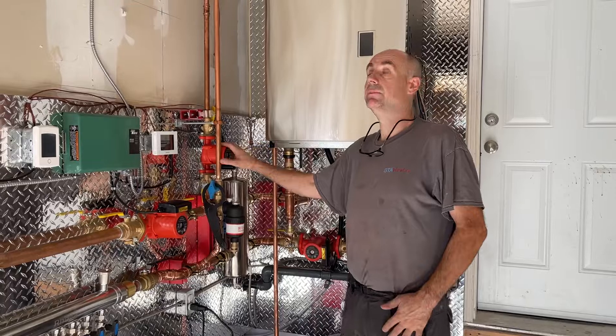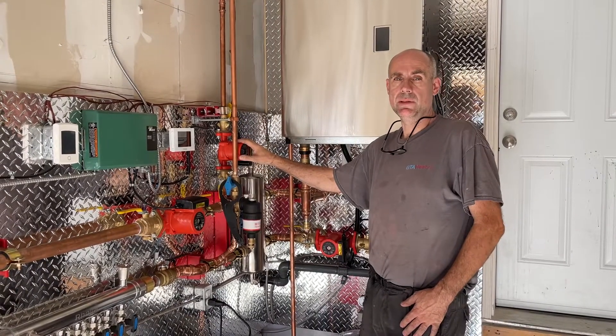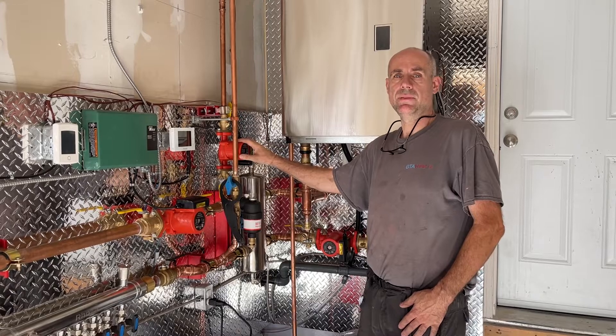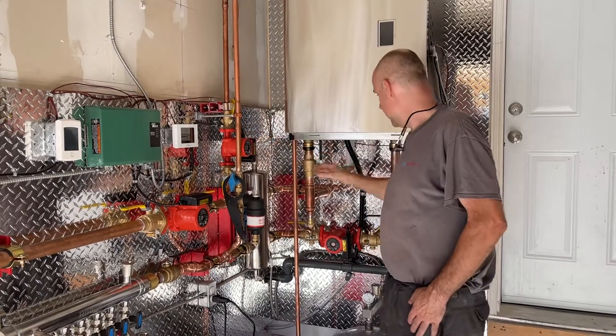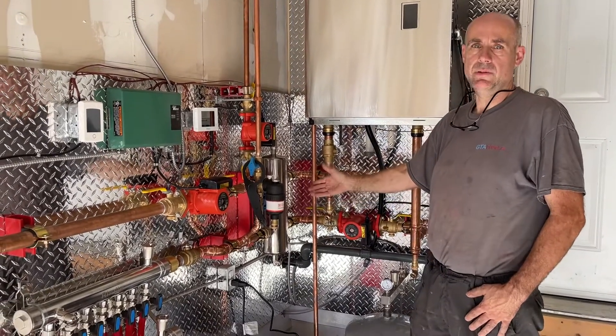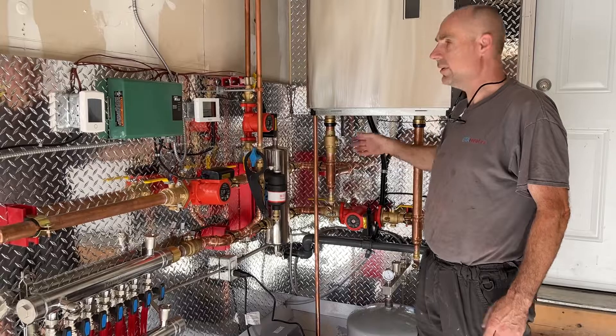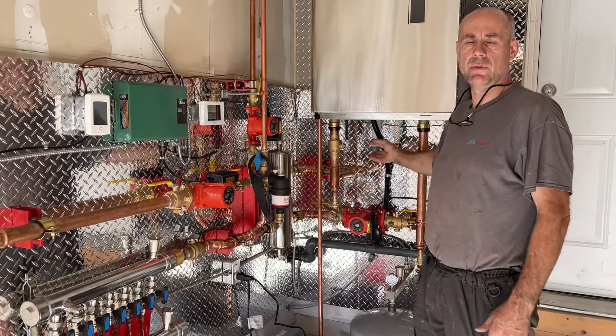The reason we need a garage heater is that when these boilers are burning gas, one of the byproducts is water vapor which condenses — hence condensing boilers — drains to the bottom of the boiler, and then needs to be drained into a drainer outside. When the boiler is working there's no problem; warm water is flowing out of it.